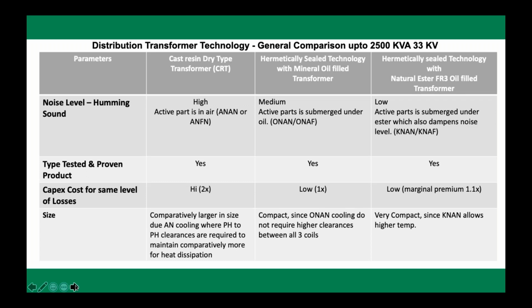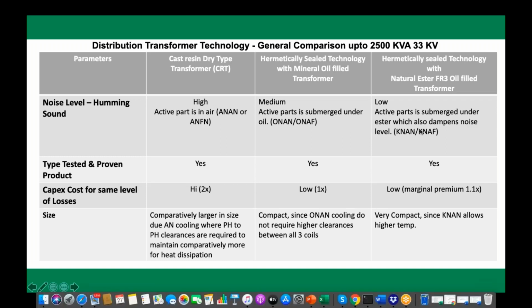Now the unique concept Adani is launching is that they want to have some pole structure and put transformers on that. Typically what CSC Kolkata has, because they don't get space. So when it comes to the space, by thumb rule you can estimate that the smallest would be a K-class filled transformer, especially a natural ester K-class filled transformer. Then second would be a mineral oil filled transformer, which is like 1:1.1, and a dry type transformer is normally 1.5 to 1.8. When it is 33 kV, then it becomes almost 2 times. Let's move to the next slide.